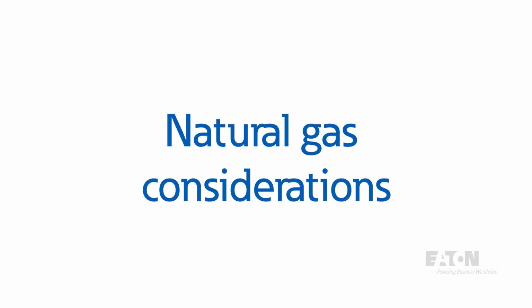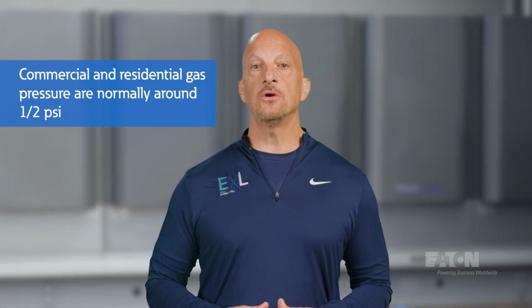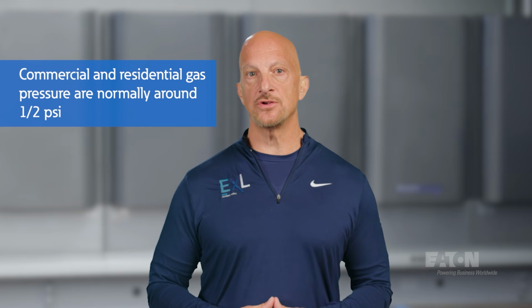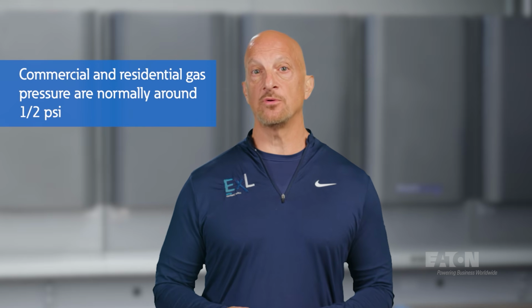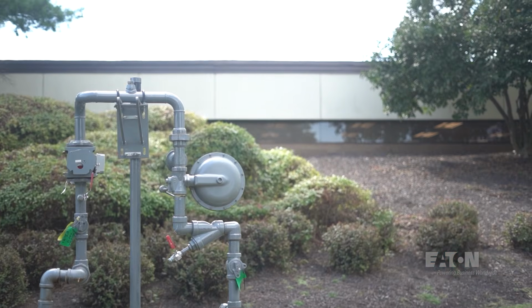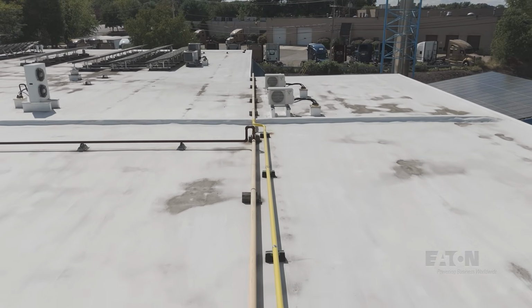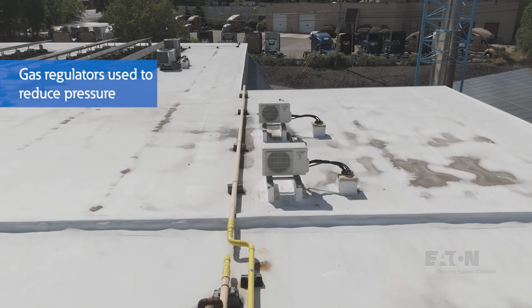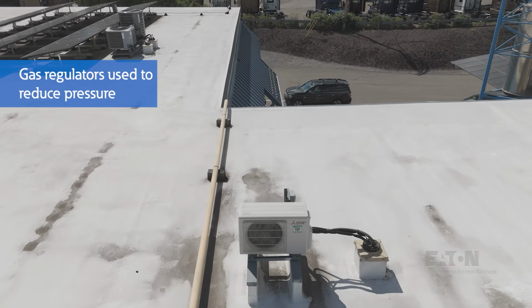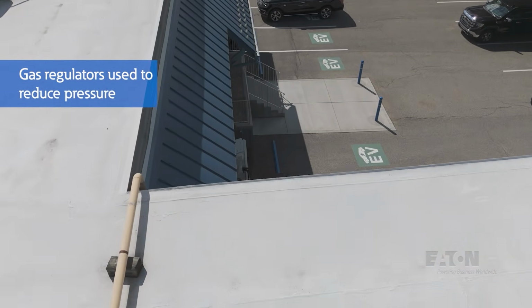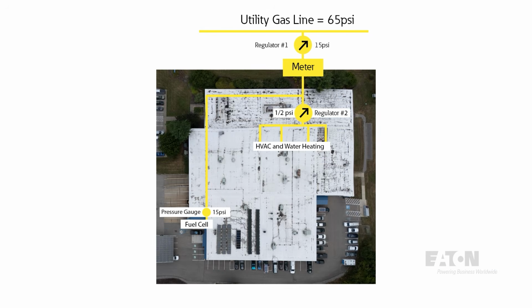One interesting thing we learned about was the pressure associated with the natural gas at our facility. We learned that the fuel cell needed 15 psi of pressure for the natural gas, but our building gas pressure was only about a half a psi. We also learned that our homes use about a quarter to a half a psi, which was surprising to all of us. With this in mind, we reconfigured our building at a higher psi to match the needs of the fuel cell, and then dropped the pressure with regulators for the other gas requirements of our building, including water heaters and HVAC equipment.